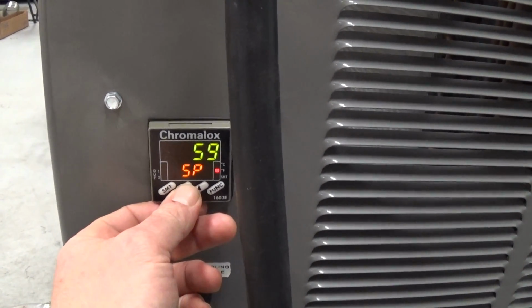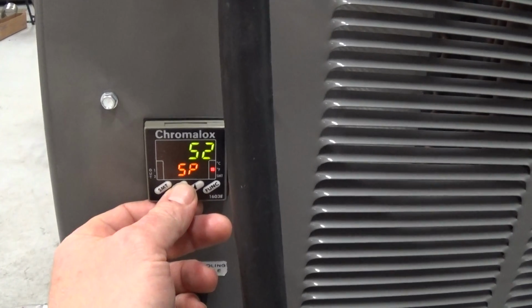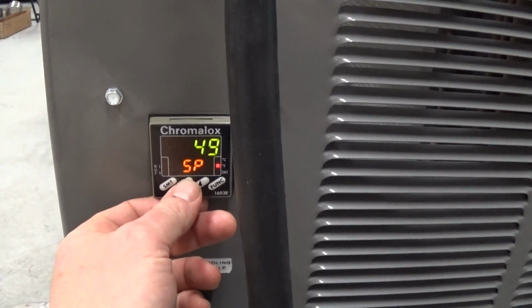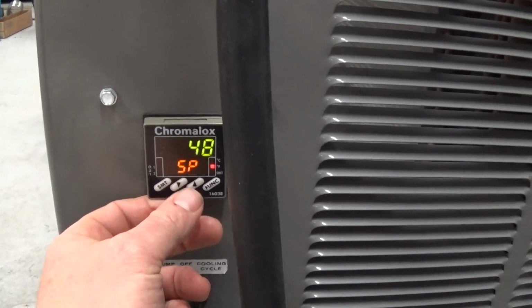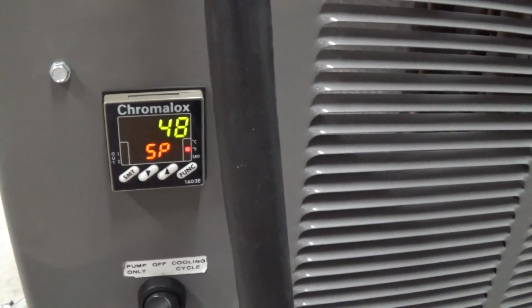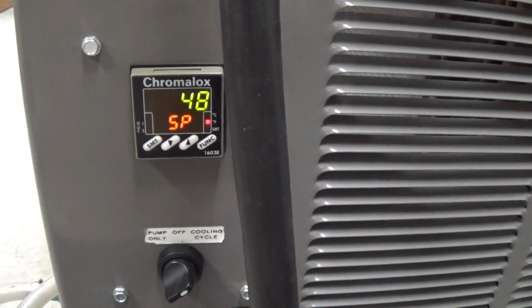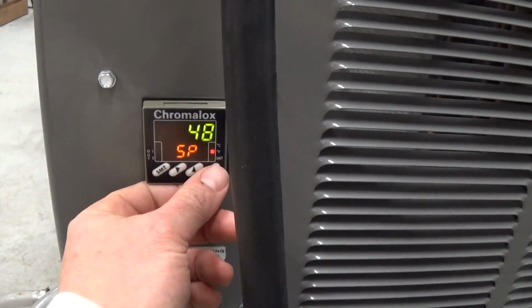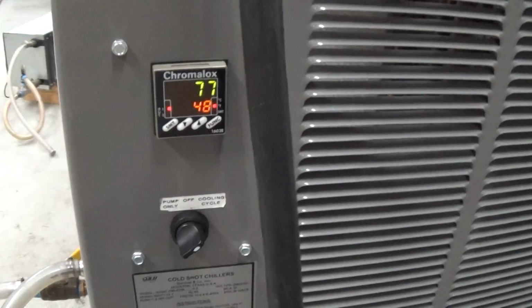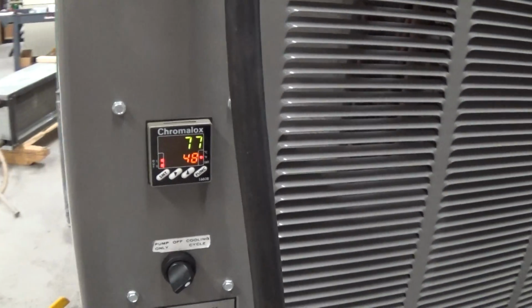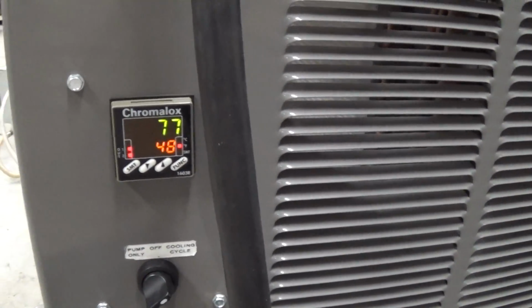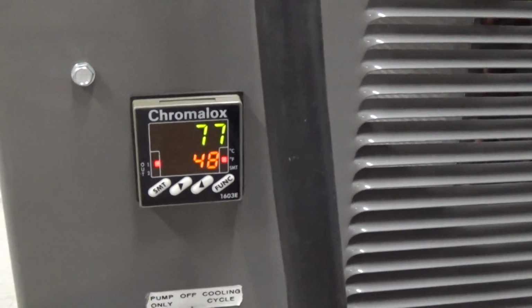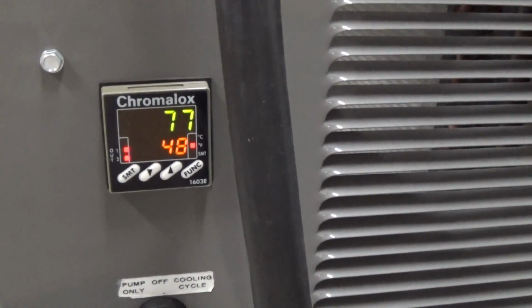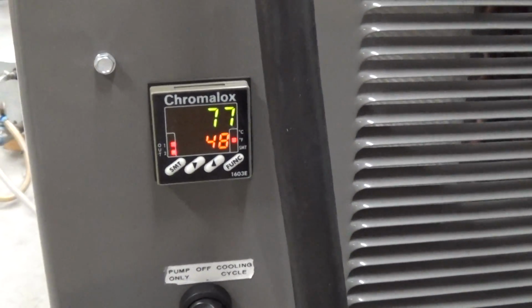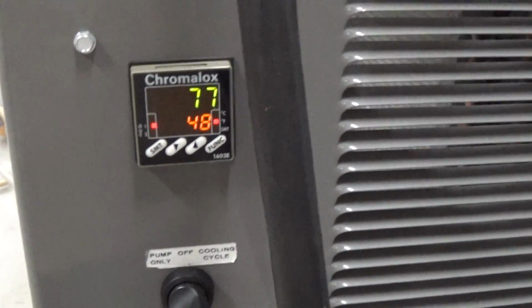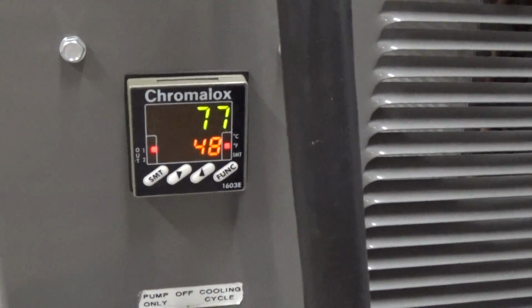I believe this customer is going to run straight water. Never run a chiller below 48 degrees set point unless it's straight water. In this case here, I'm going to bring it down to 48 for the test. And so we're starting to chill now, and those indicator lights simply show that the compressor is on, and it's showing us that we're a little bit out of range right now because I brought the set point down so much lower than what the existing temperature was.